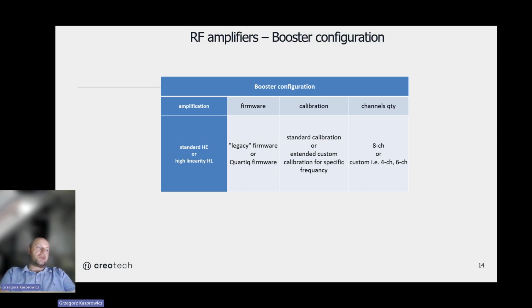You can also ask for standard calibration, which we do at something like 150 megahertz, or extended calibration for specific frequencies. I mean calibration of the interlocks, because interlocks are implemented as very fast RF power detectors, and they respond depending on frequency. So you can ask us to calibrate for specific frequencies, so the dBm values you enter during operation are valid for that certain frequency. You are really encouraged to recalibrate yourself if you want to. It's easy: you simply run some serial port commands or MQTT commands to calibrate.